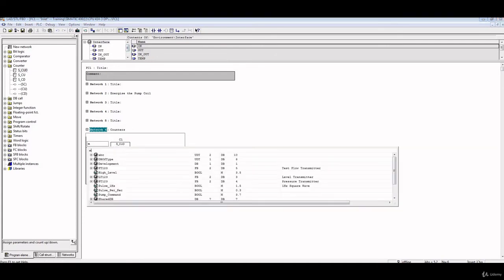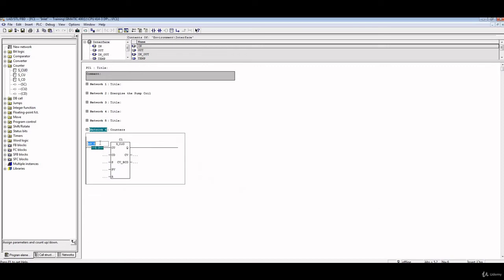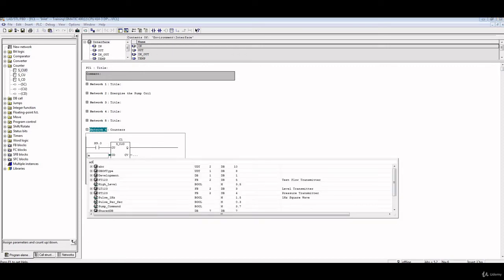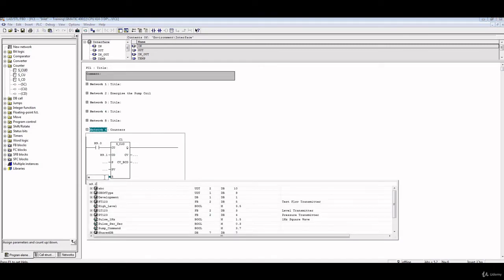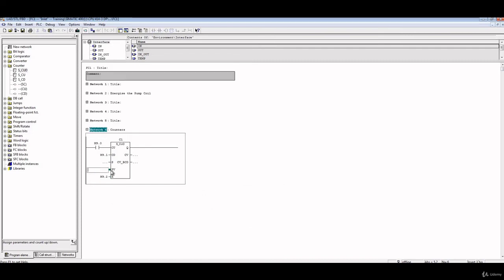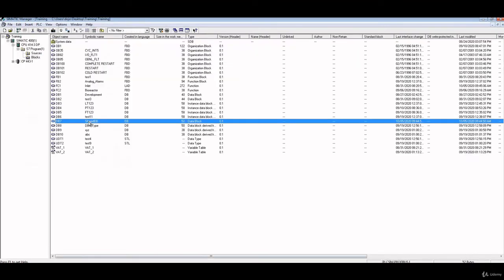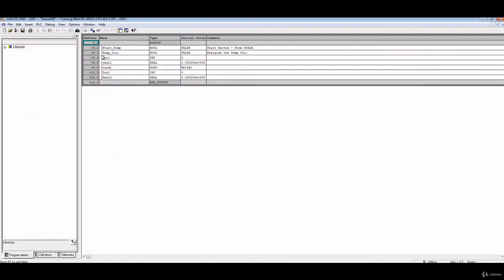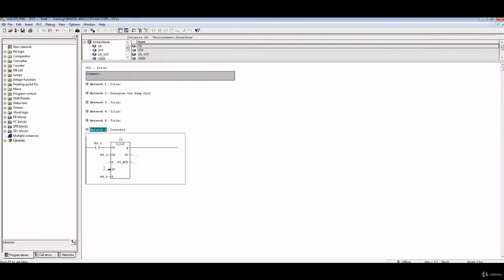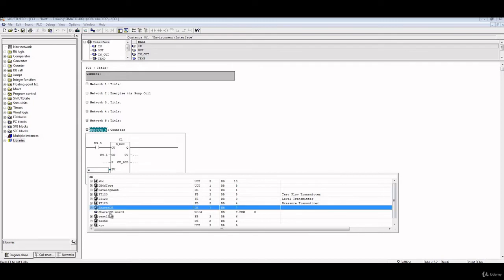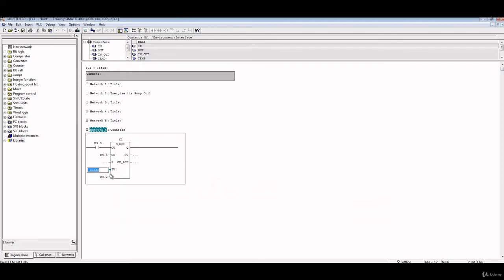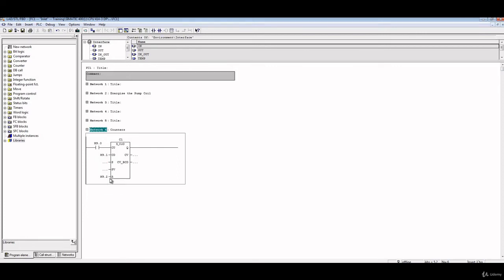To make it more illustrated, I'll just give it some values. So I'll put here M9.0, and here M9.1, and here M9.2. And then here in PV we should put a word. You see here the input should be a word value. So if you go to our shared DB, we'll see what word we have. We have here word one. So we'll go back here and then put here shared DB and then word one.